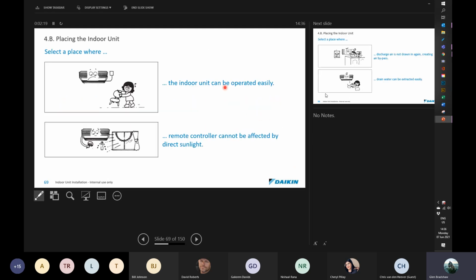Placing the indoor unit. This is the important part for the installation. The indoor unit must be able to operate easily, so it's very important that you put it in a location where it's going to be able to give a good account of itself in cooling down or heating up a room. The remote controller cannot be influenced by direct sunlight, so do not place remote controllers on walls that have direct sunlight on them. We've seen this done a number of times, and it causes the unit to overcool areas.